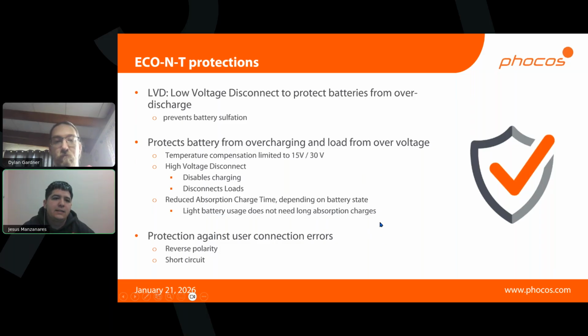Here are some ECO-NT protections. It has LVD disconnect, which protects the battery from over-discharge. The other protection is against overcharging, with temperature compensation limited to 15 volts or 30 volts depending on whether you have a 12 volt or 24 volt system. It also has a high voltage disconnect, which disables charging once it reaches that threshold, as well as disconnecting the loads at that time.